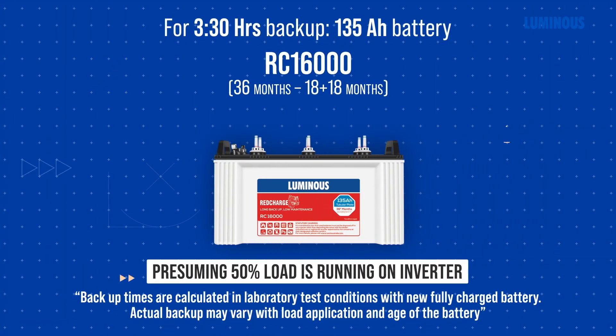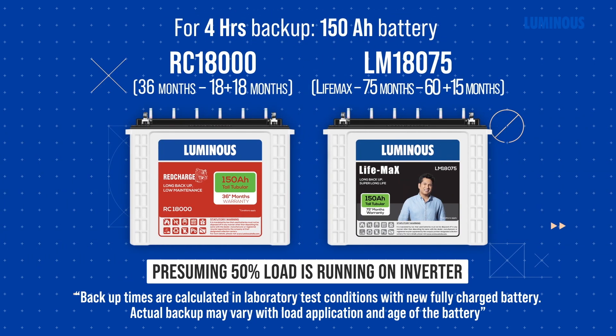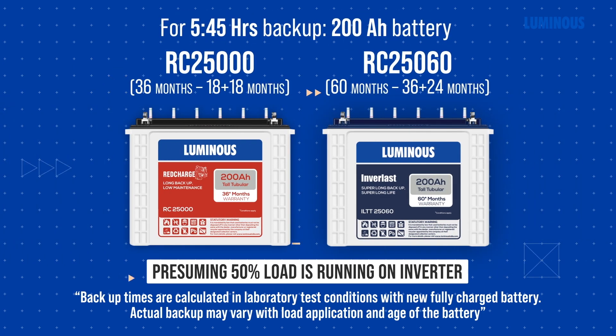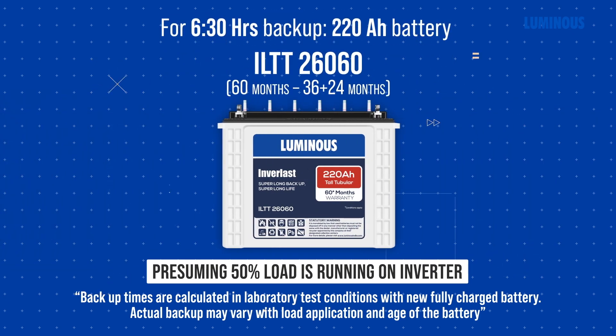Let us now see which battery is correct for these inverters. For 3 hours 30 minutes backup, a 135 AH capacity battery is required. For 4 hours backup, a 150 AH capacity battery is needed. For 5 hours backup, a 180 AH capacity battery is needed. For 5 hours 45 minutes backup, a 200 AH capacity battery is required. For 6 hours 30 minutes backup, a 220 AH capacity battery is required.